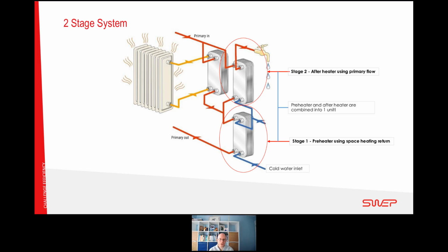On average, and it obviously depends on the system setup, the system demand at the time, hot water demand and space heating demand, you can achieve up to 10 degrees lower temperature compared with a parallel system. So this is obviously quite interesting for everybody that's involved in the district heating scheme: owners, operators, end users, and so on.